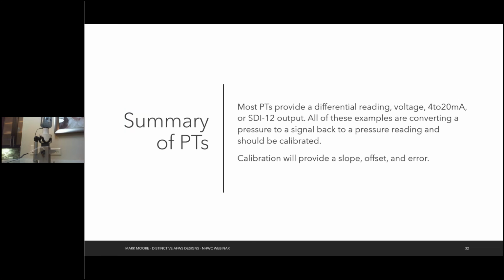So a quick summary of PTs is that most PTs provide a differential reading, a voltage, a 4 to 20, or an SDI12. Those are different ways they send the data. But at the end of the day, all of these examples are converting pressure to a signal back to a pressure reading and should be calibrated. When you calibrate, you're going to get a slope, an offset, and an error.